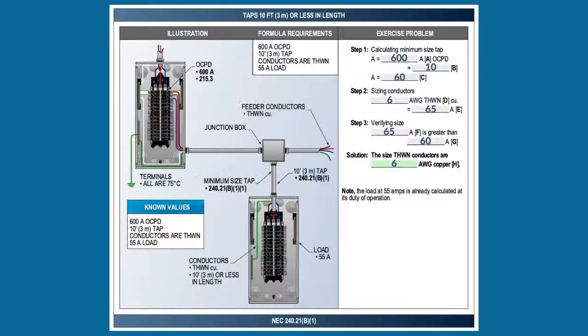Now, as you look at this, I've got a 600 main upstream, 10 foot or less. I'm going to divide by 10, that gives me 60 amps. And guess what? I need to go look at Table 310.16. When you go over there, the next size above that is 65 amps, which is a number 6. So I have to have at least a number 6 conductor going down to that panel board from the tap.